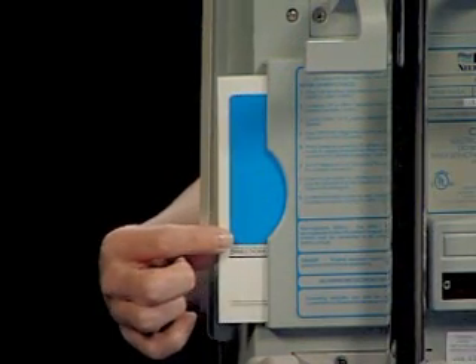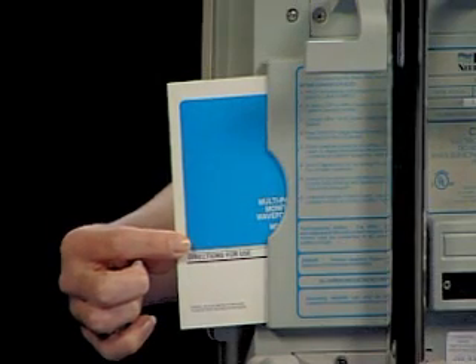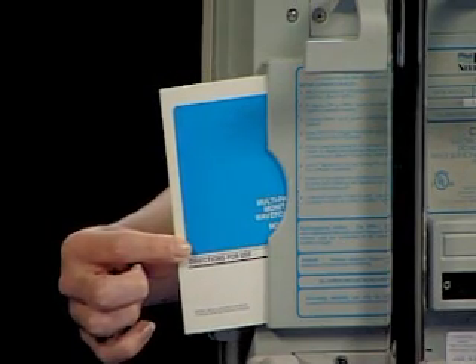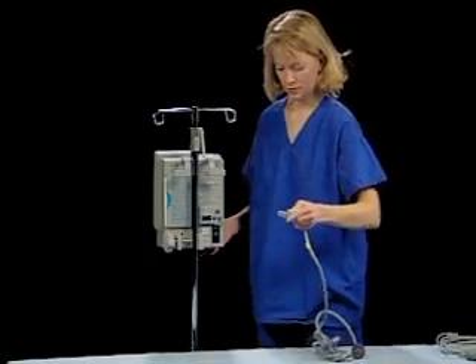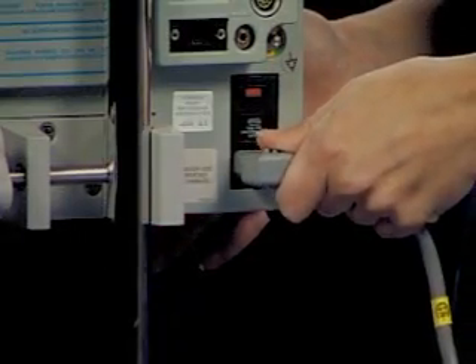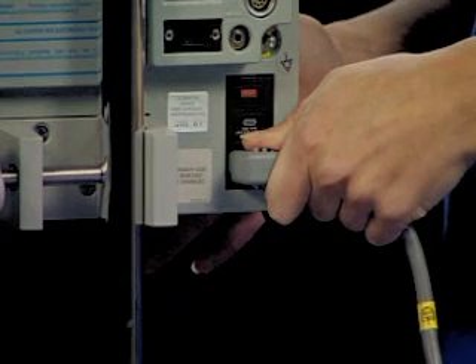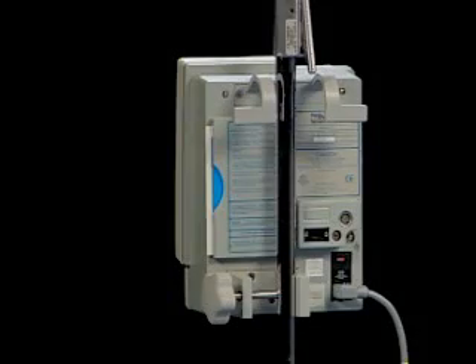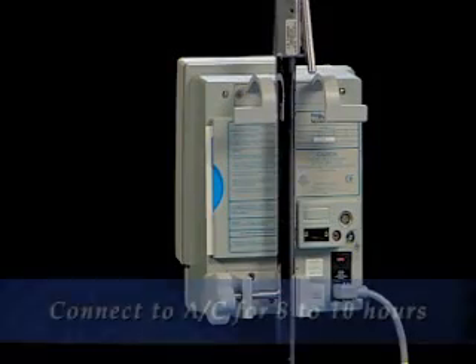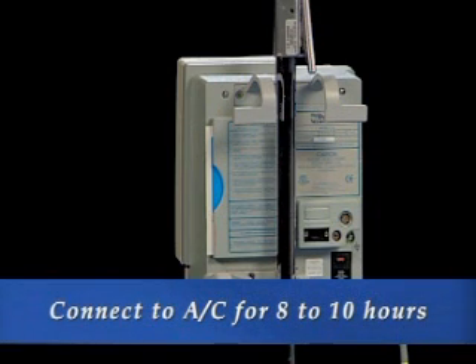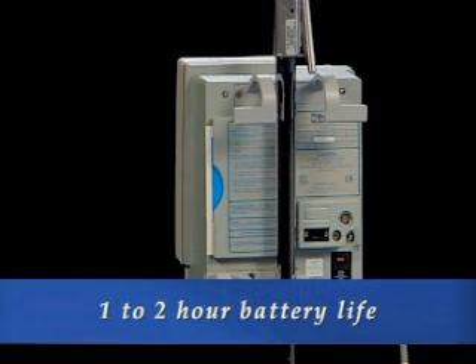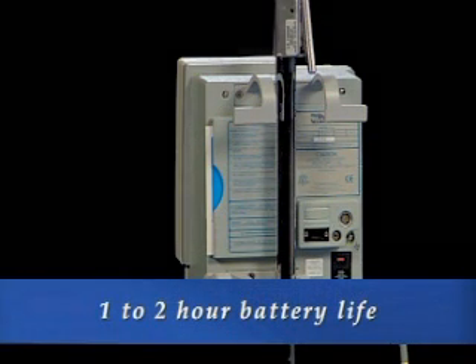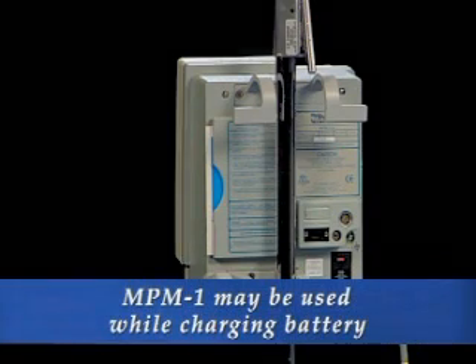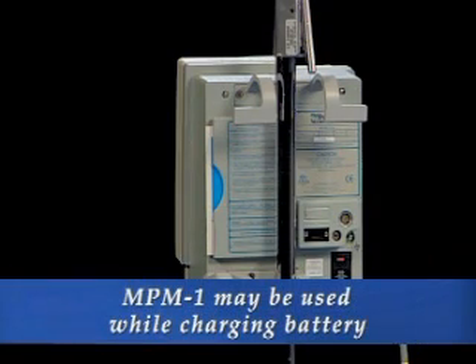Also found on the back of the monitor is a pocket, which provides a storage space for the user directions for use. Basic setup instructions can be found here. The AC power cord is connected to the monitor and placed into a grounded AC outlet. To ensure a fully charged battery, the monitor should be plugged in at all times unless transporting a patient. The battery must be connected to AC power for 8 to 10 hours to achieve a full charge. A fully charged battery provides 1 to 2 hours of monitor use while unplugged. The MPM-1 may be used on AC power while charging.